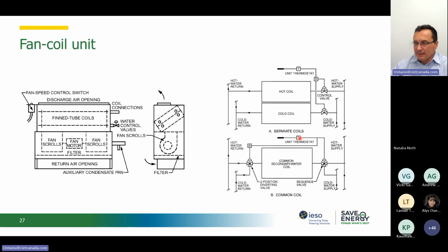So the two-pipe system seems to be the most frequent one. If you have the four-pipe system, we can have a two-coil or the common coil as a system. Very rarely are we going to see the two-coil in multi-residential buildings. This is more of a specific application where we need to have cooling and heating pretty much at the same time. So hospitals, museums, maybe.